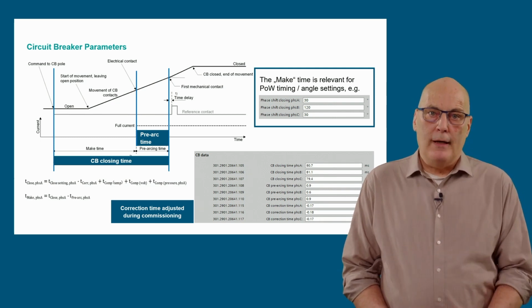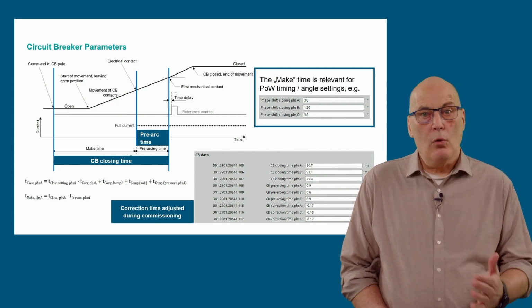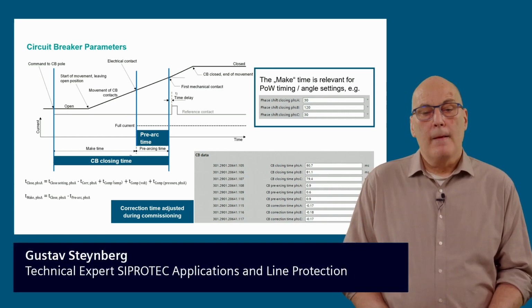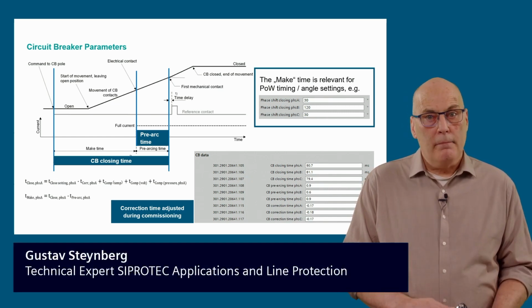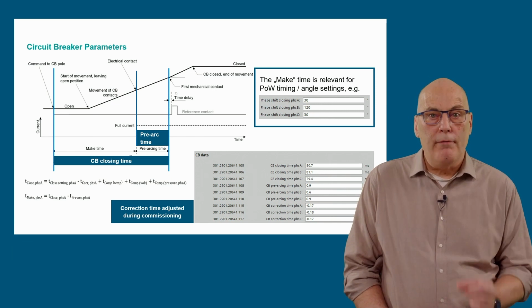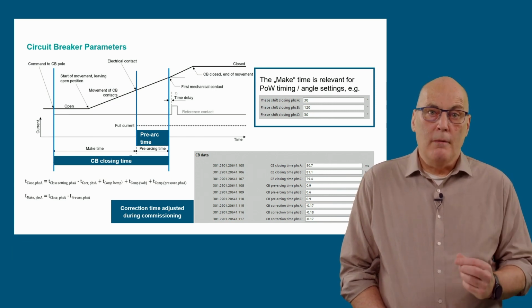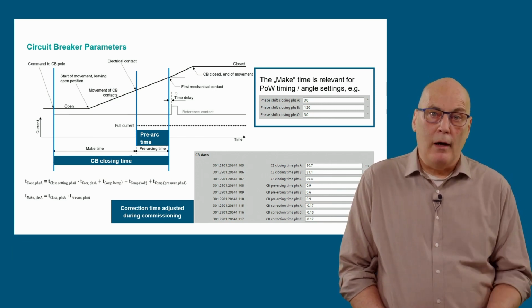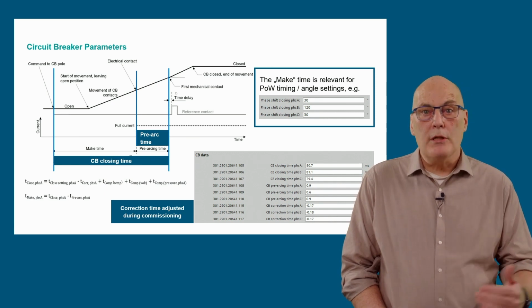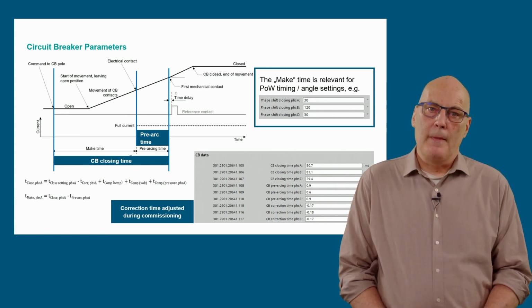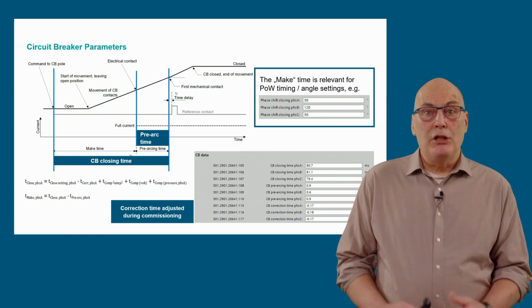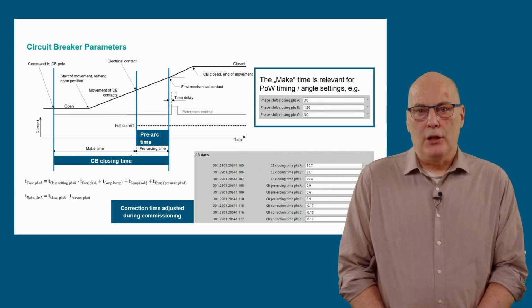The measured closing time is with reference contact or auxiliary contact. The make time is relevant for timing of the output contacts. The make time is measured with current or voltage on the load side after closing. This will be shown again in Chapter 3, Commissioning and Adjustment.